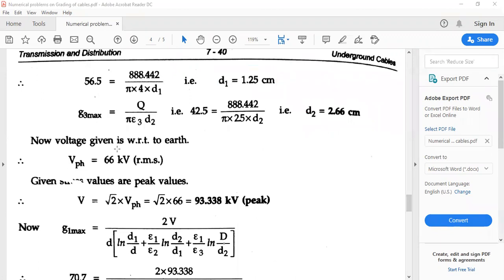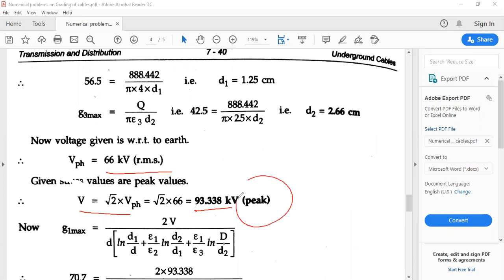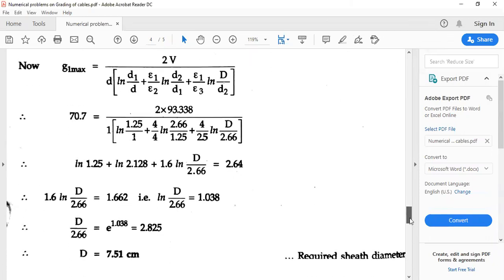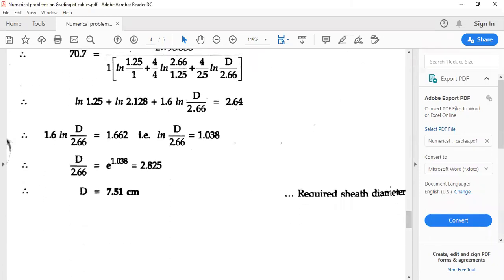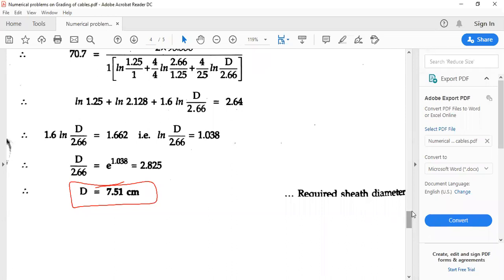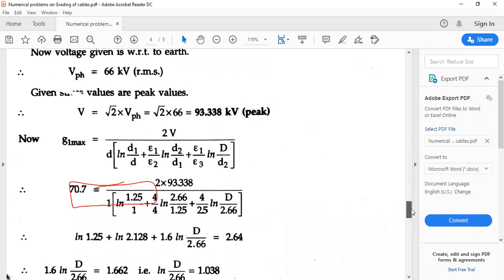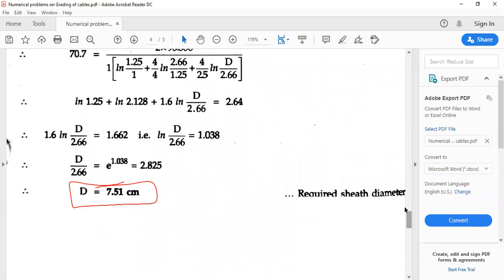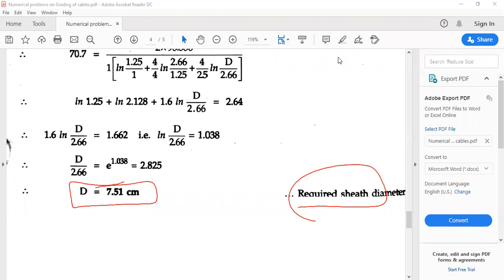The voltage is 66 kV RMS, giving a peak value of 93.338 kV. G1 max is given directly, and substituting into the formula gives capital D as 7.51 cm. That is the required sheathing diameter for this problem.